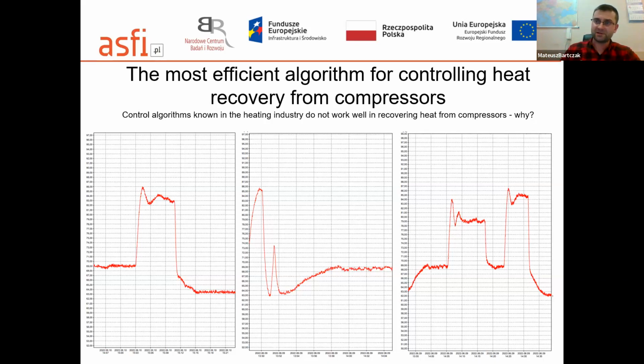And a different situation when the water has a higher temperature: the power of the heat exchanger is lower. So in this situation, oil could go to the radiator, and you will lose available energy. This graph shows the response of the power control algorithm to change. The rate of change of water flow as a function of oil temperature is the same as the rate of change of temperature on the oil side.